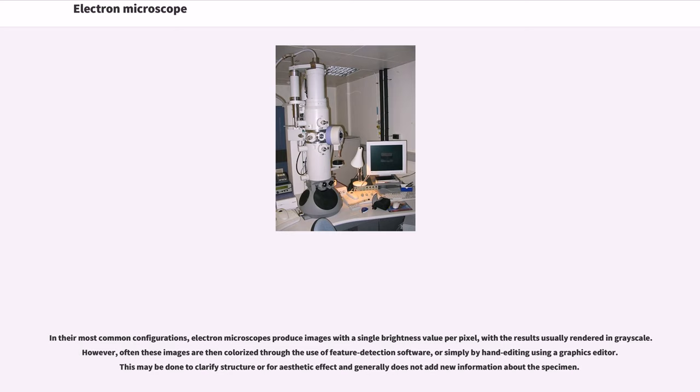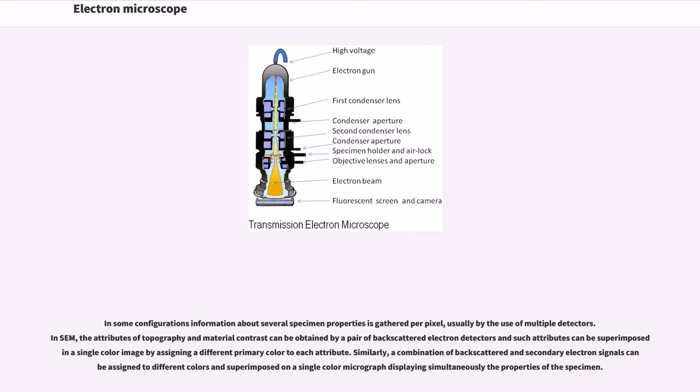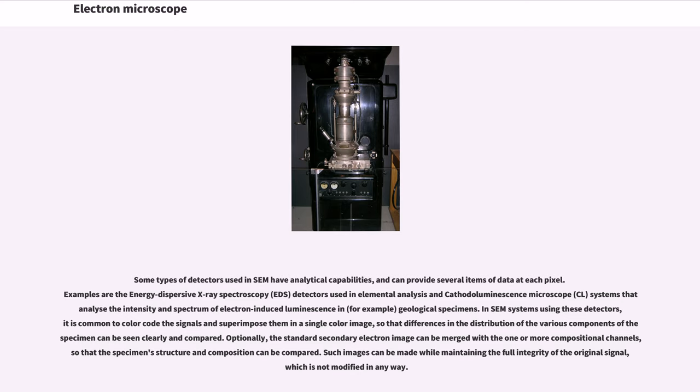This may be done to clarify structure or for aesthetic effect and generally does not add new information about the specimen. In some configurations information about several specimen properties is gathered per pixel, usually by the use of multiple detectors. In SEM, the attributes of topography and material contrast can be obtained by a pair of backscattered electron detectors and such attributes can be superimposed in a single color image by assigning a different primary color to each attribute. Similarly, a combination of backscattered and secondary electron signals can be assigned to different colors and superimposed on a single color micrograph displaying simultaneously the properties of the specimen.